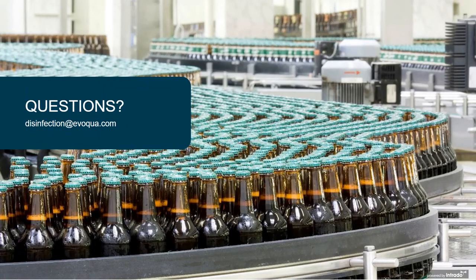Wonderful. And then we have a question asking, what flow rate do you have UV equipment? Okay, so UV can be used anywhere from a few gallons a minute to millions of gallons per day. The largest system that Evoqua makes for that is probably about 20 million gallons a day in one reactor. But it also depends on the water quality and the required disinfection limits.